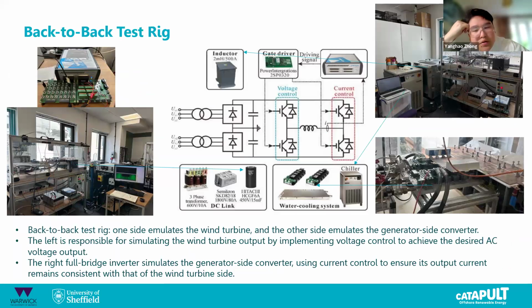In my experiment, I am using a test bench with two microhenry inductive loads, and the system output voltage is 200 volts and the current amplitude is 440 amps. We are using the Infineon 1.7 kilovolt, 1 kiloamp IGBT half bridge module with 6 chips in parallel. One side of my test bench emulates the wind turbine, and the other side emulates the generator side converter, and the right side uses current control to make sure its output current is the same as the wind turbine side.